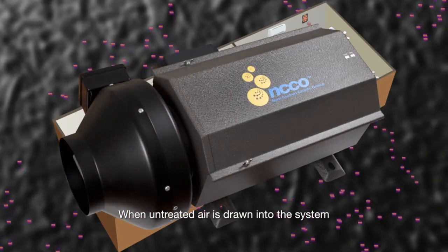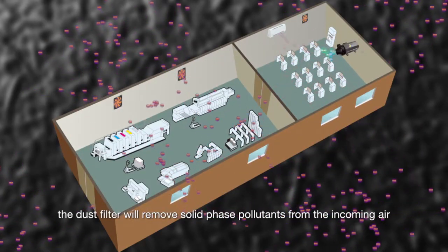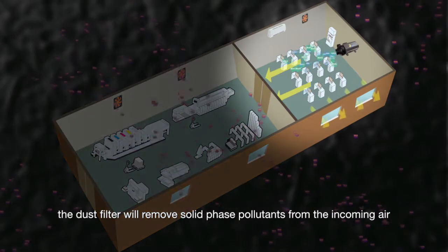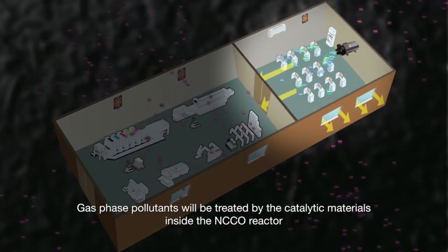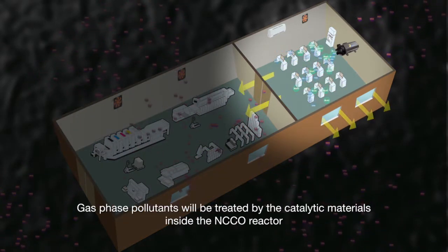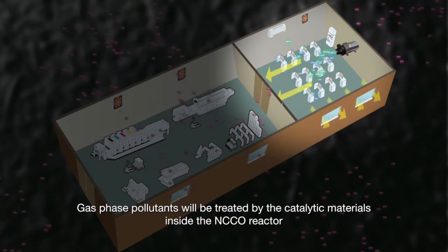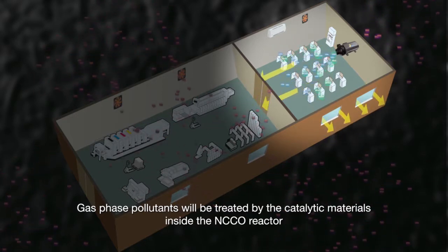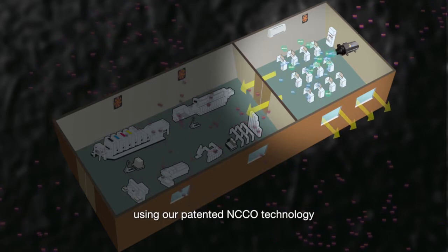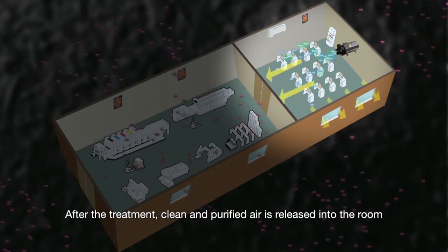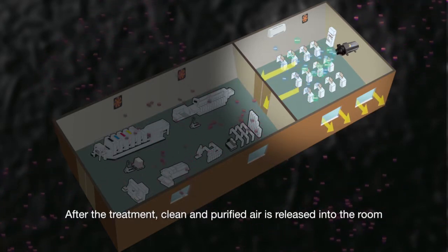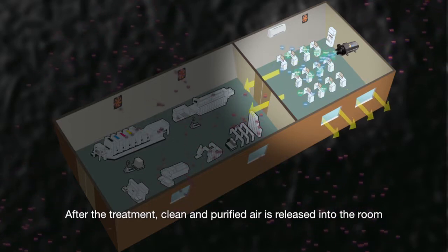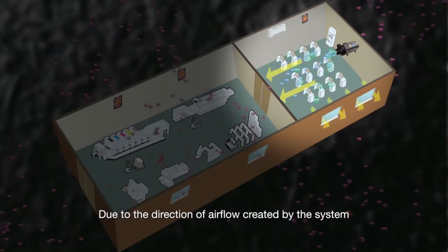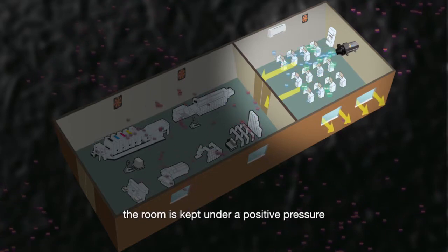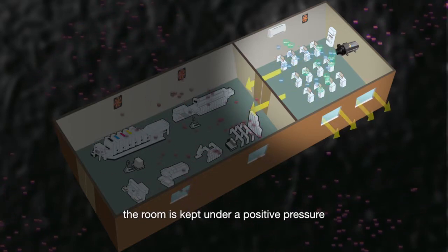When untreated air is drawn into the system, the dust filter will remove solid phase pollutants from the incoming air. Gas phase pollutants will be treated by the catalytic materials inside the NCCO reactor using our patented NCCO technology. After the treatment, clean and purified air is released into the room. Due to the direction of airflow created by the system, the room is kept under a positive pressure.